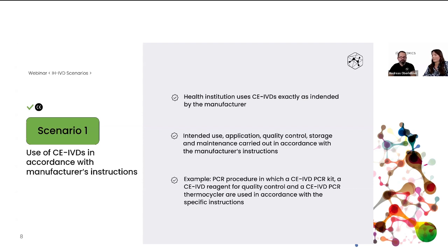Okay, so that means that every device anyways is a CE-IVD device. Therefore, a manufacturer has already done the whole work on certifying the product, proving the efficacy, the efficiency, and also the safety of the device. And it also fulfills already the IVDR. By the way, CE-IVD, we are still in the transition phase with many devices. So CE-IVD might also include CE-IVDs under the old directive as well. So IVDR or IVDD devices are still seen as equivalent from the regulatory or from the legal perspective. But we have transition periods on that, which you need to consider, of course, as a manufacturer as well.